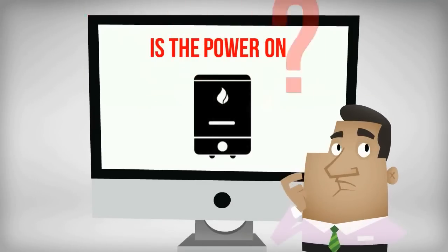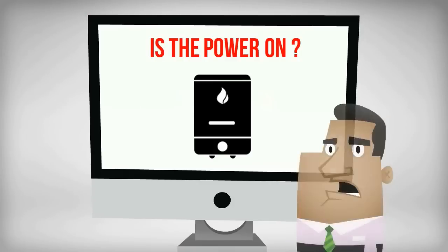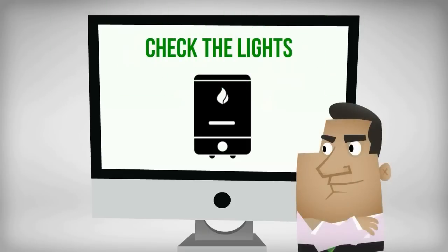Is the power on? It might seem obvious but if there's no power going to the boiler it won't be able to heat up the water. Check that the lights on your boiler are on and that the pressure is around one bar.